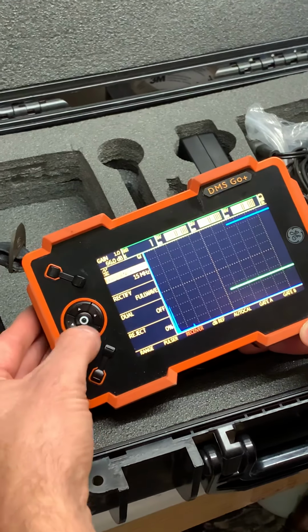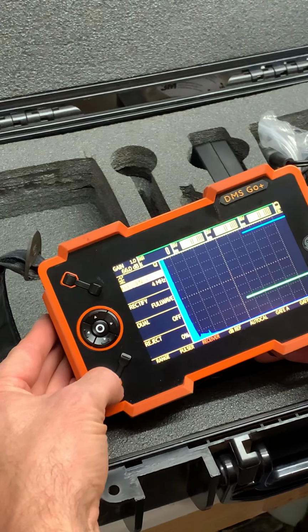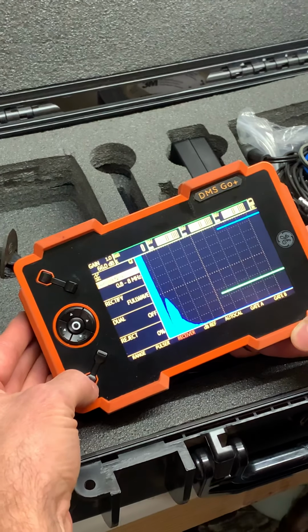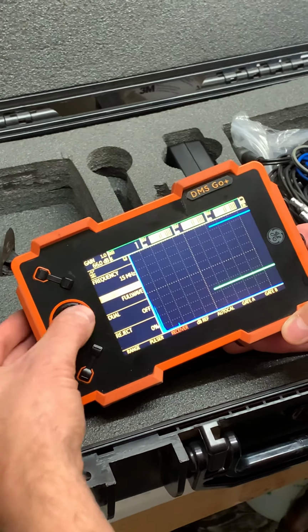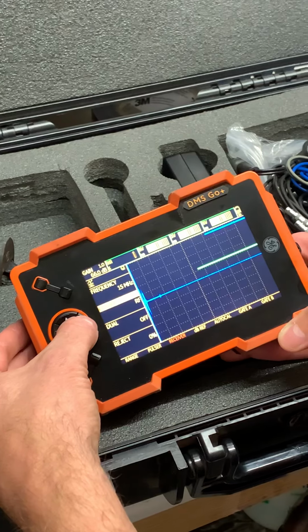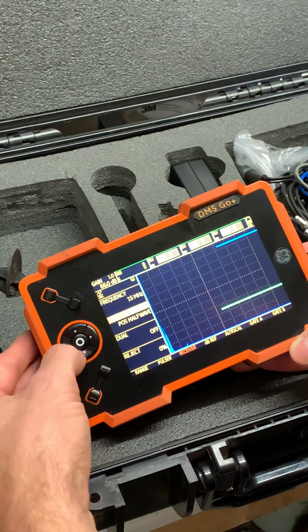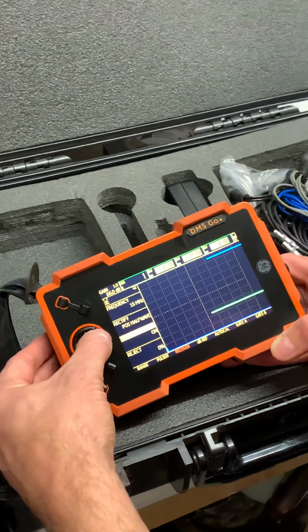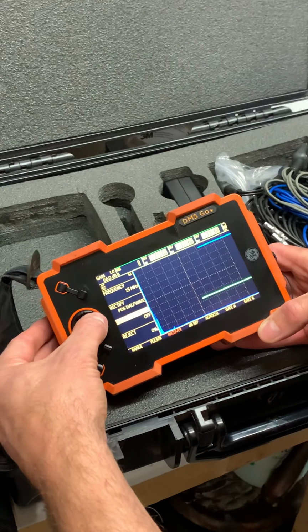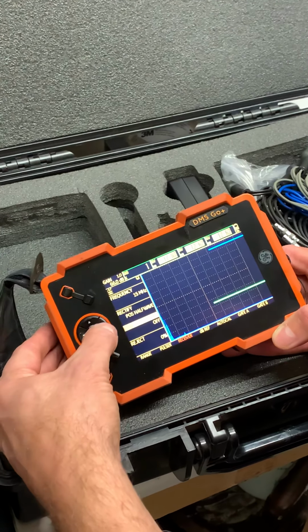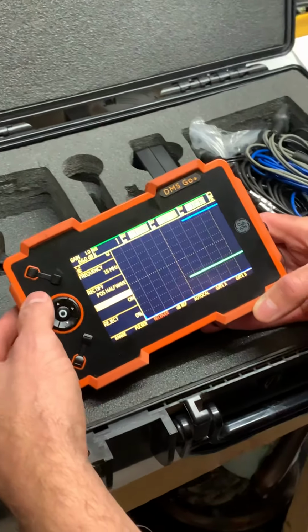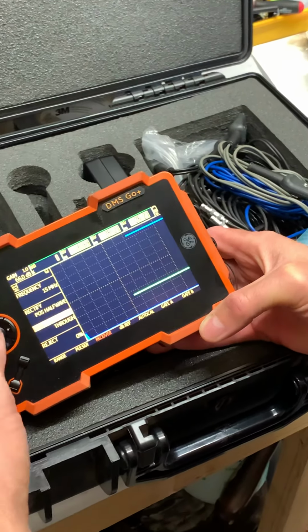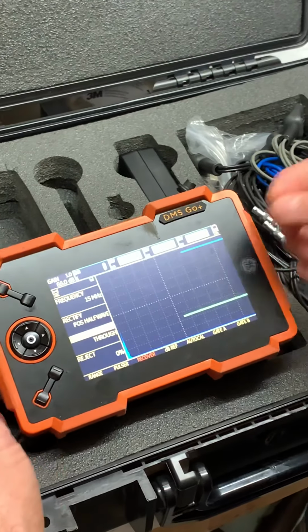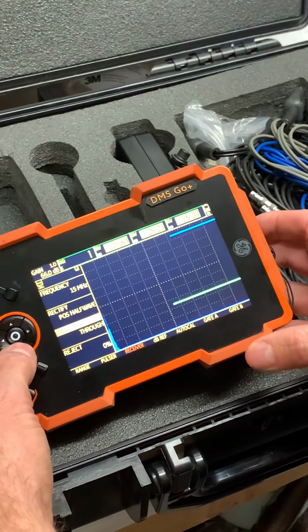I can go up and change my frequency to match my probe. I can change my rectifying from full wave to RF to negative wave. And I can go from dual through or dual off. So if I've got a single crystal probe, that's what I use; for a twin crystal probe, that one. If I've got two probes either side of a part, like on some aerospace applications, I'll use through.